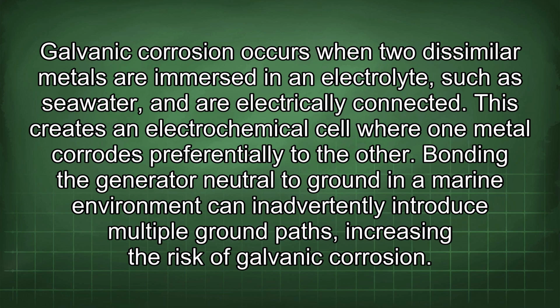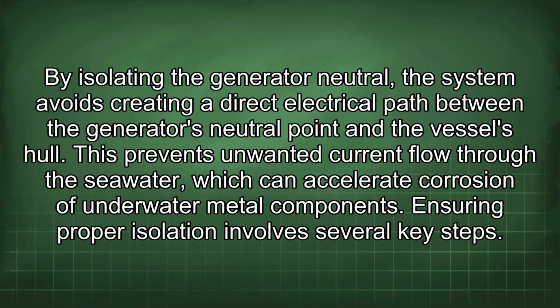Bonding the generator neutral to ground in a marine environment can inadvertently introduce multiple ground paths, increasing the risk of galvanic corrosion. By isolating the generator neutral, the system avoids creating a direct electrical path between the generator's neutral point and the vessel's hull. This prevents unwanted current flow through the seawater, which can accelerate corrosion of underwater metal components.